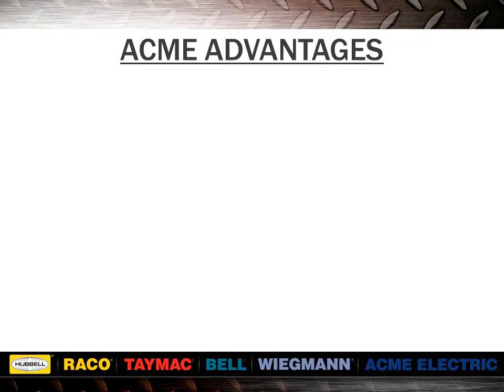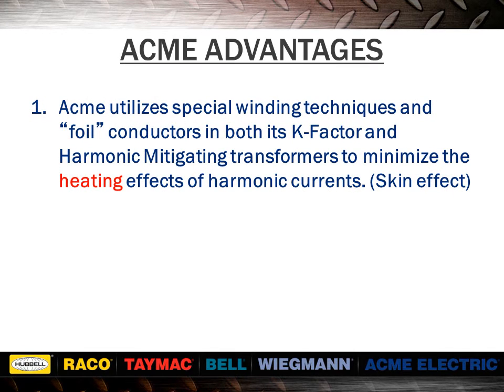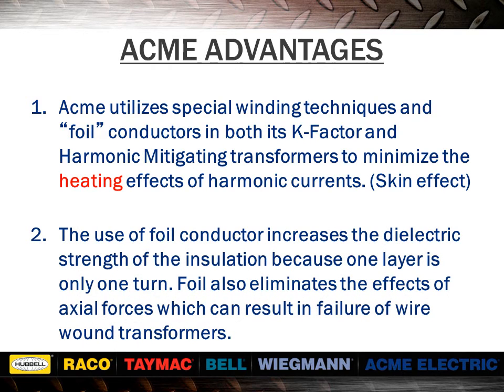Acme transformers have definitive advantages. Acme utilizes special winding techniques and foil conductors in both its k-factor and harmonic mitigating transformers to minimize the heating effects of harmonic currents. The use of foil conductor increases the dielectric strength of the insulation because one layer is only one turn. Foil also eliminates the effects of axial forces, which can result in failure of wire wound transformers.